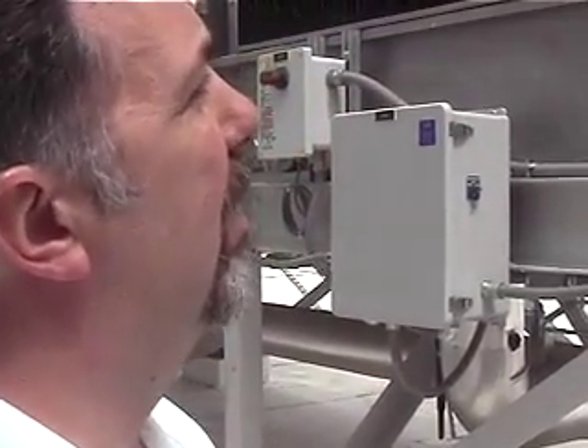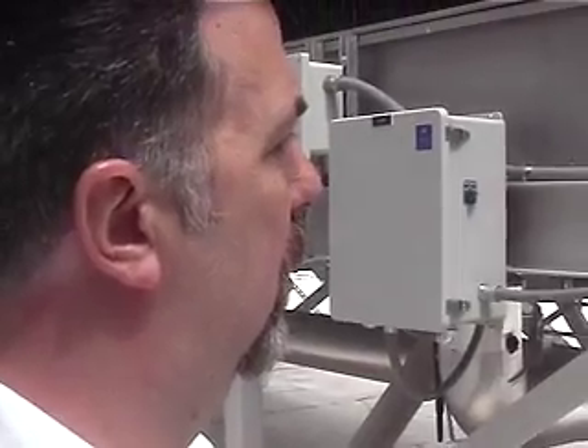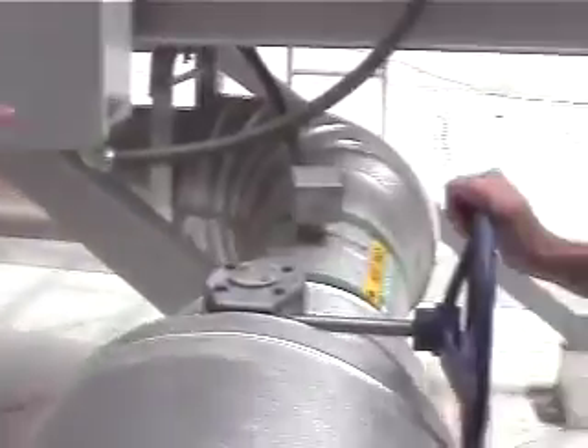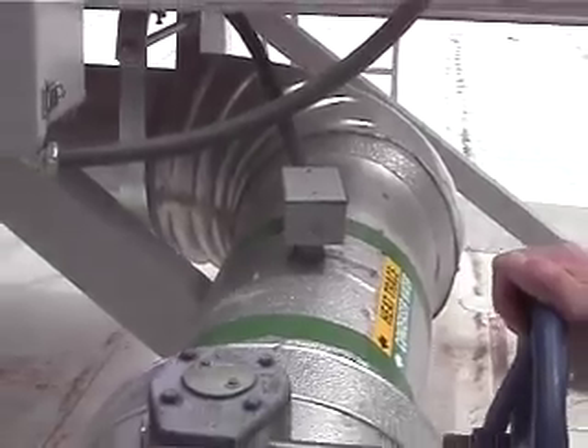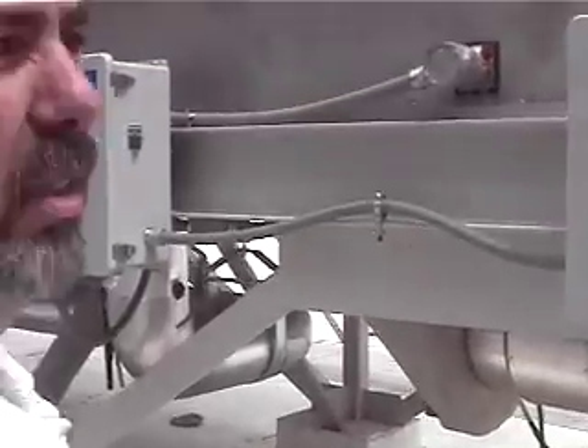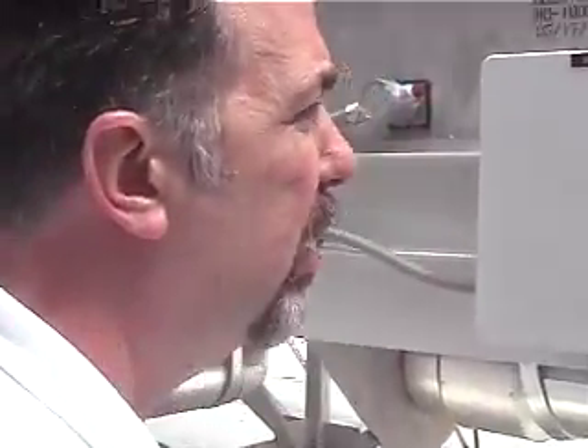There's his Eco. We ran it through all his paces, they work really good. Temperature sensors on the sump of each of the towers, so we're monitoring what each one's doing. And the sump temperature, we're controlling that off the contact closure, to maintain water temps. It's all controlled off the air handler discharge air, to prevent freezing.